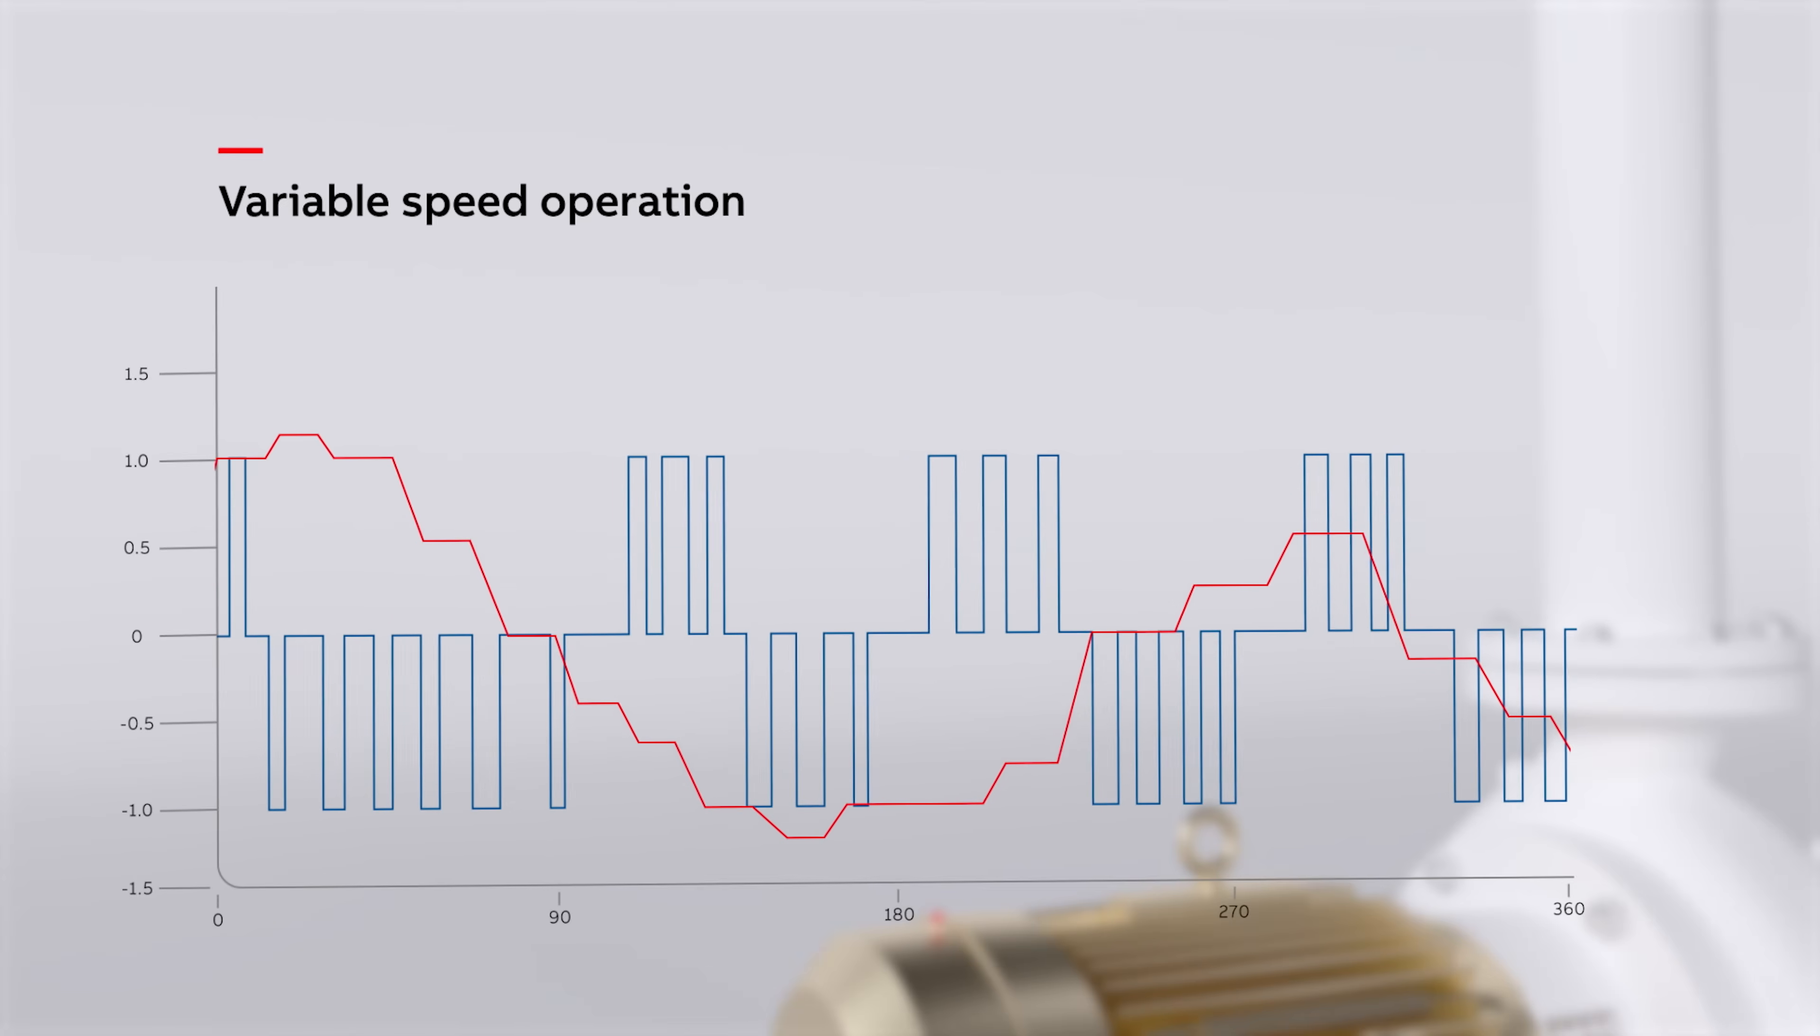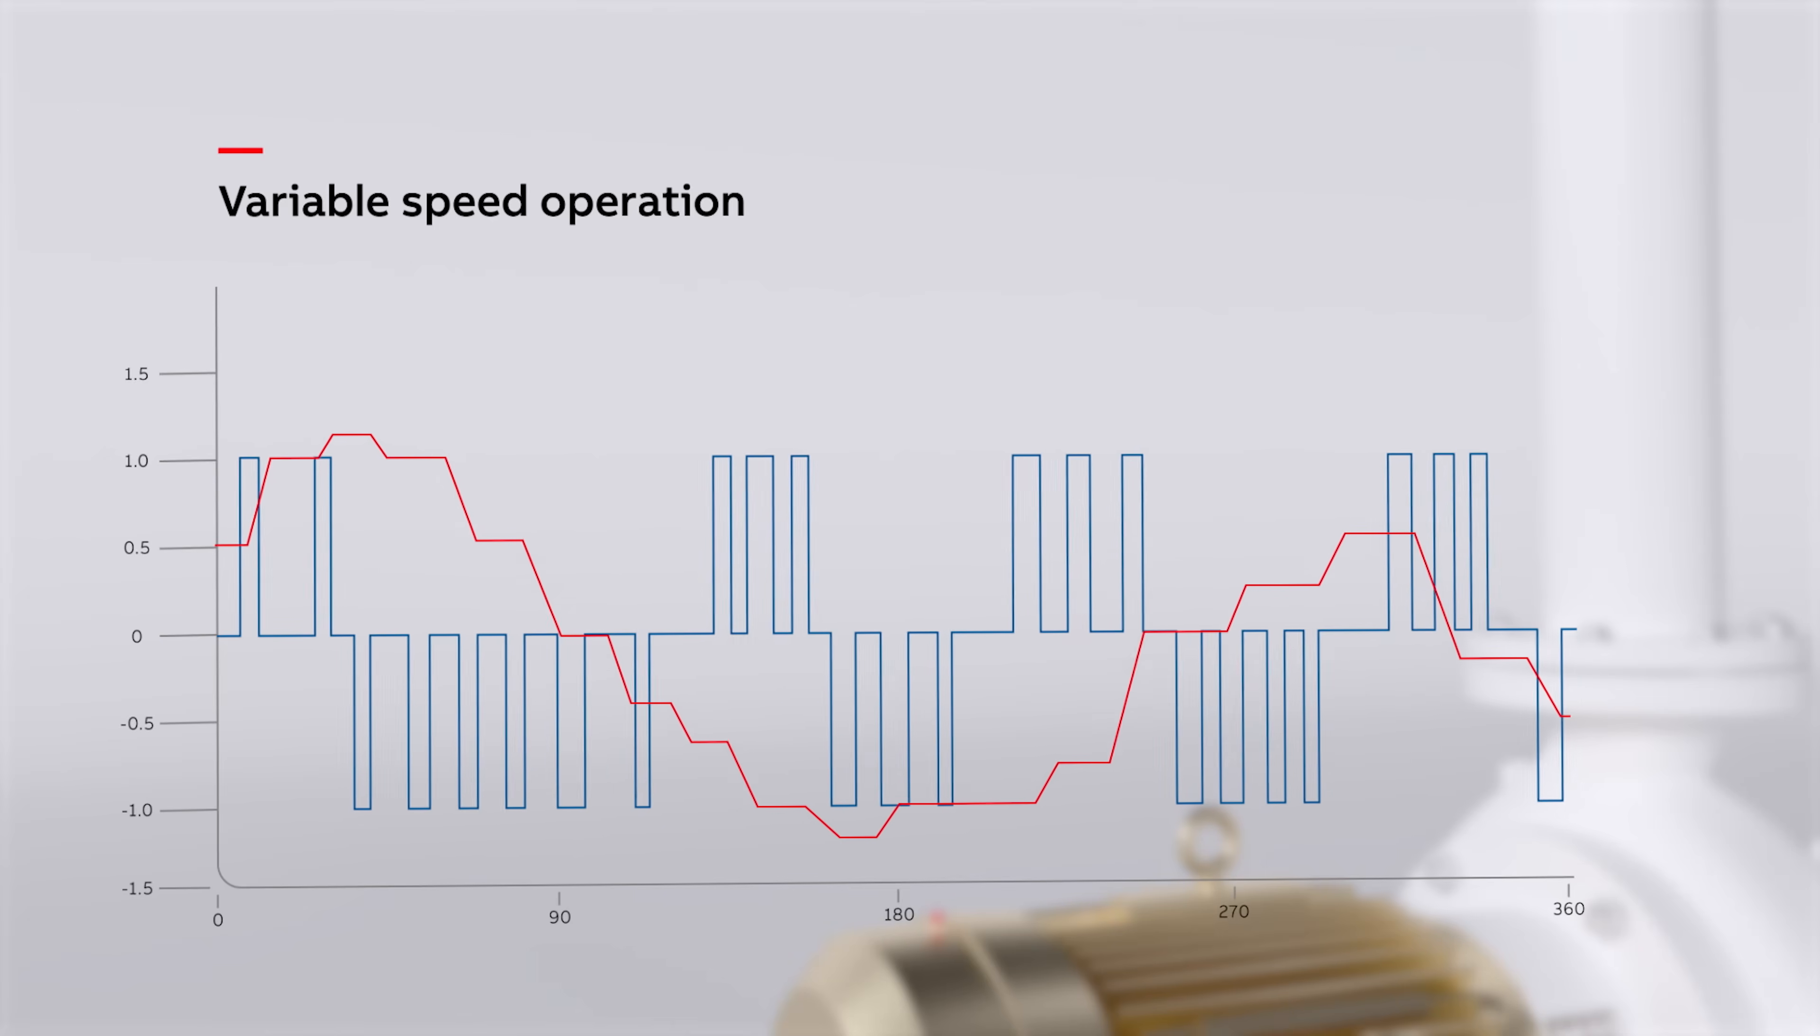When motors are controlled by a VFD, the power is converted to a series of high-frequency pulses that emulate the approximate sine wave, but is not exact with high harmonics. The result is an imbalance known as common mode voltage.